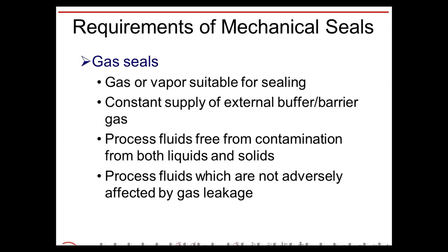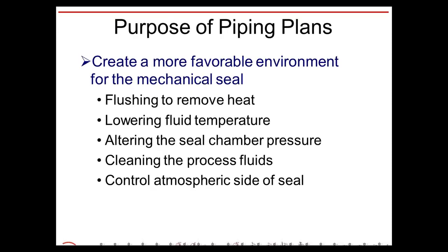trouble than it's worth. You want to make sure that the process fluids are free from contamination, so very, very clean gas, nice and dry, filtered if possible. Process fluids should not be adversely affected by the gas leakage. You don't want to have any reactions in your pump.